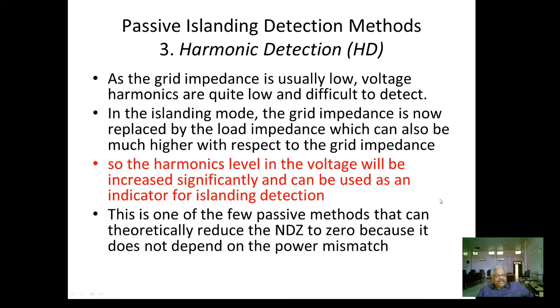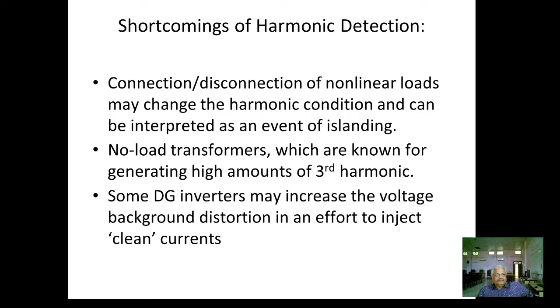Now, what are the shortcomings of this harmonic detection? Connection or disconnection of a nonlinear load may change the harmonic condition and can be interpreted as an event of islanding. This is the first thing. No-load transformers, which are known for generating a high amount of third harmonic, may also mislead the protection. Some DG inverters may increase the voltage background distortion in an effort to inject clean current. This may also cause a problem for harmonic detection.